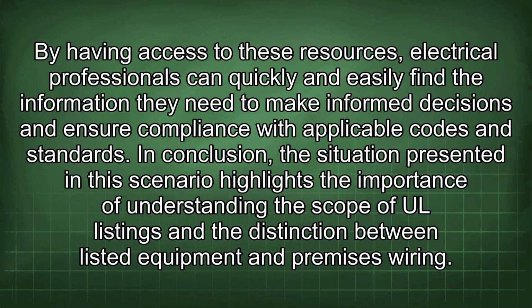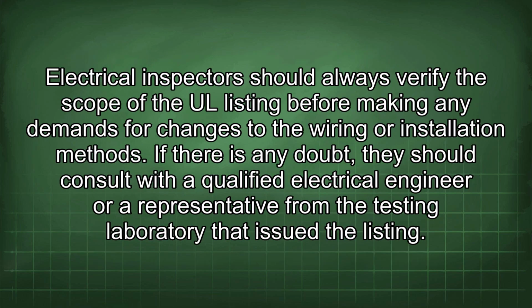In conclusion, the situation presented in this scenario highlights the importance of understanding the scope of UL listings and the distinction between listed equipment and premises wiring. Electrical inspectors should always verify the scope of the UL listing before making any demands for changes to the wiring or installation methods. If there is any doubt, they should consult with a qualified electrical engineer or a representative from the testing laboratory that issued the listing.